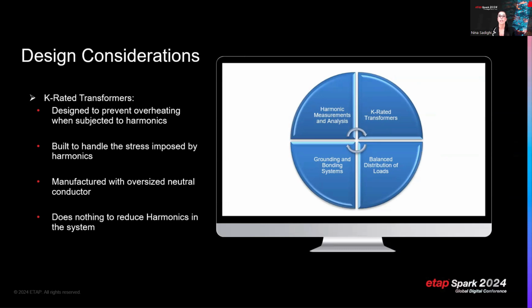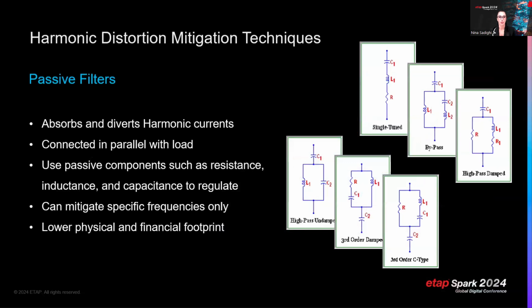K-rated transformer is a good design solution, which really can withstand harmonics, but it's not mitigating. It's manufactured with oversized neutral conductors. It does nothing for mitigating the system, but it's built to handle the stress imposed by harmonics. Another mitigation technique is passive filters. They do absorb and divert harmonics, but at a very specific frequency that we specified for it. And it's a lower cost and a lower footprint. It is connected in parallel with the load.